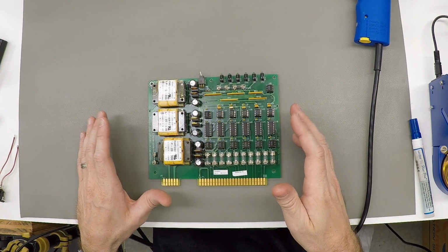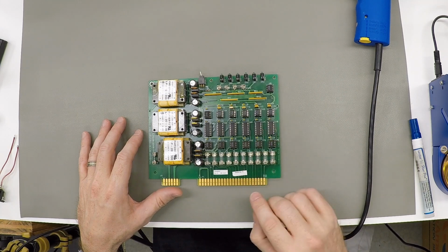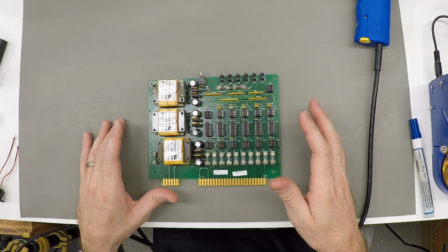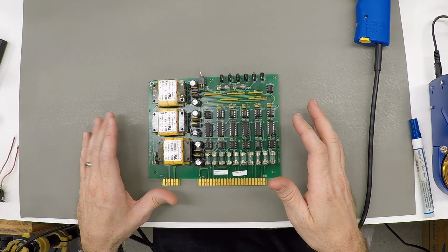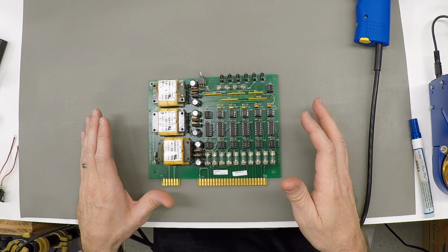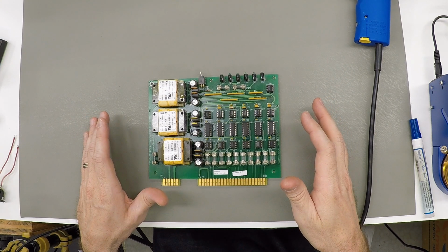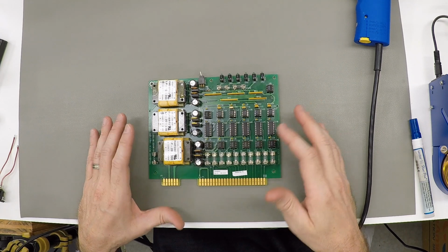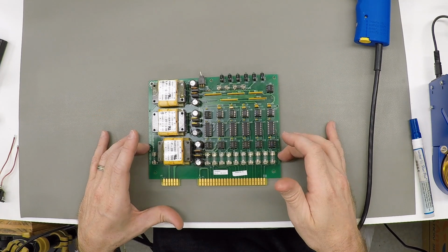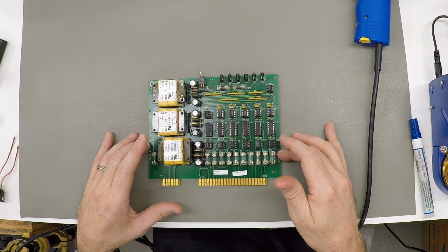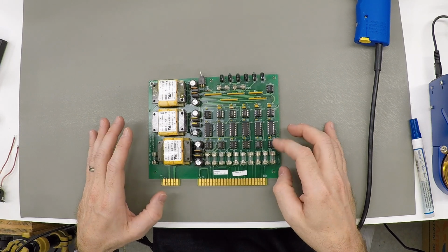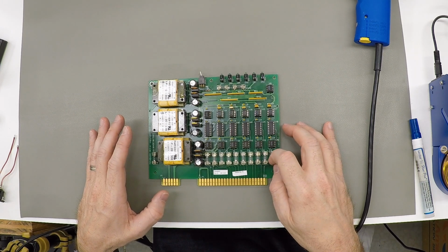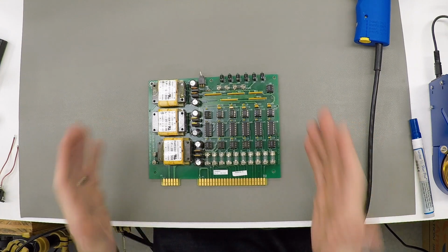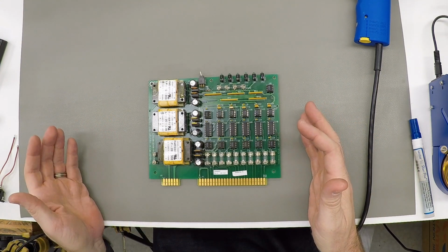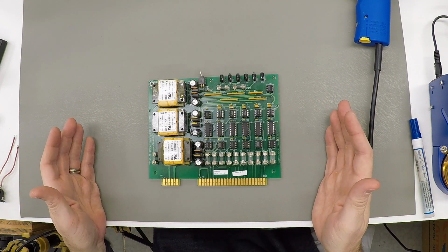So why would we want 6 independent power supplies? The answer is that DMX operates in a noisy environment. You've got huge dimmer packs potentially doing pulse width modulation on multi-kilowatt lighting circuits, which generates a lot of noise. Plus you're dealing with long cable runs in a building or even an outdoor venue, where the sending equipment, the amplifying equipment, and the lighting instruments themselves are all on different circuits.